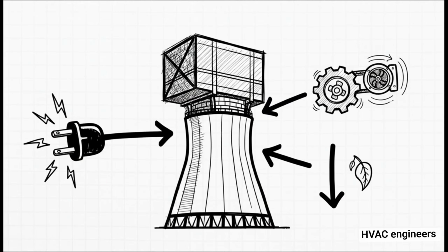Here's the crucial point: when companies are pressured into hiding that plume just for visual reasons, a process called plume abatement, they accidentally create a massive, ironic energy penalty. To stop the condensation, they have to install hybrid dry sections just to actively reheat the exhaust air. This requires bigger fan motors, way more electricity, a larger physical footprint, and a ton more steel. By suppressing a harmless water plume just to look green to the neighbors, they actively ruin the pure efficiency of evaporative cooling and increase the system's actual carbon footprint.